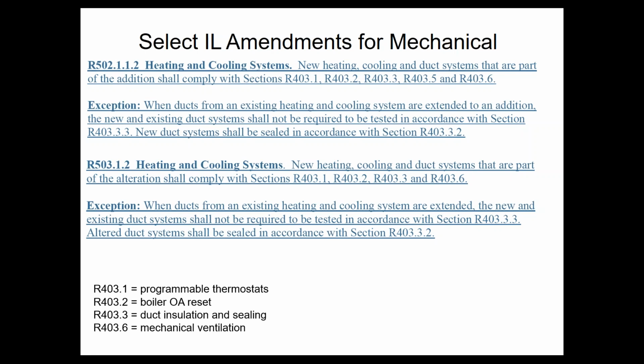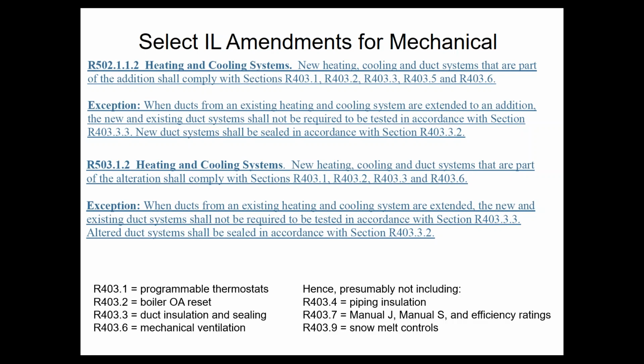What you don't have to do is the pressure testing when you seal the duct. It wouldn't be fair to make you pressure test 10 feet of new duct on the entire system when you didn't install the entire system. And then it just completely ignores a few other things. So presumably you don't have to do them, like pipe insulation on a retrofit or load calc on a retrofit, although you probably should.